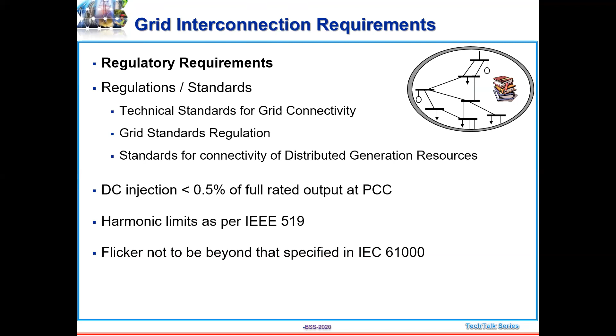This is not maintained by many of the inverter systems currently in place. They should be capable of operating in the frequency range 47.5 to 52 hertz, because they should not get disconnected when frequency fluctuations occur. Since conventional generators are not there, if these renewables also get tripped out, there will be a huge imbalance in load-generation balance and consequent collapse of the grid. So they should be capable of operating in this 47.5 to 52 hertz region, and should be able to deliver rated output at 49.5 to 50.5 hertz. These are regulatory requirements.